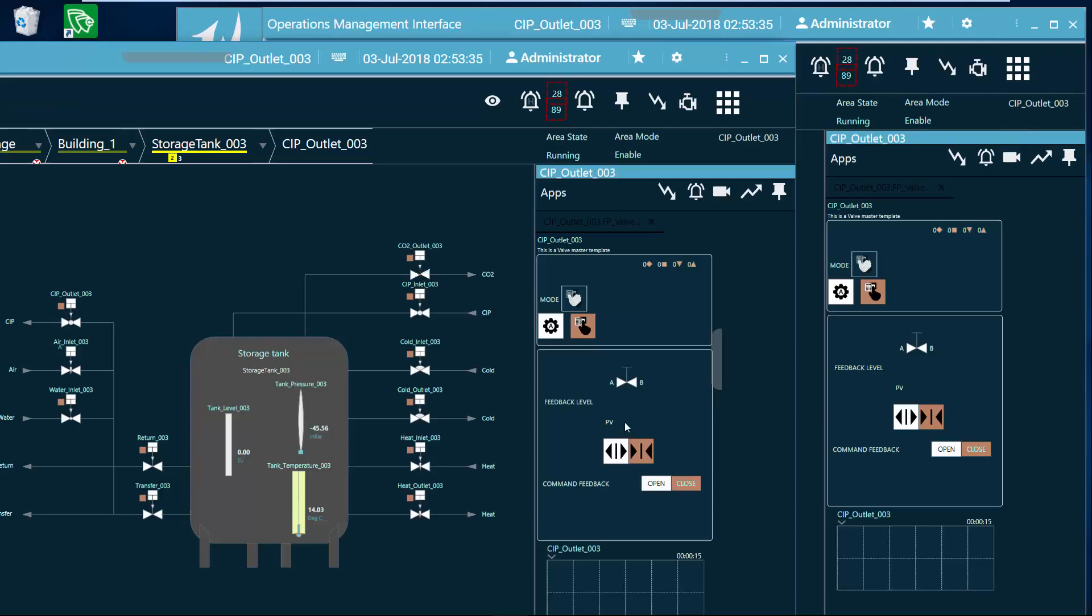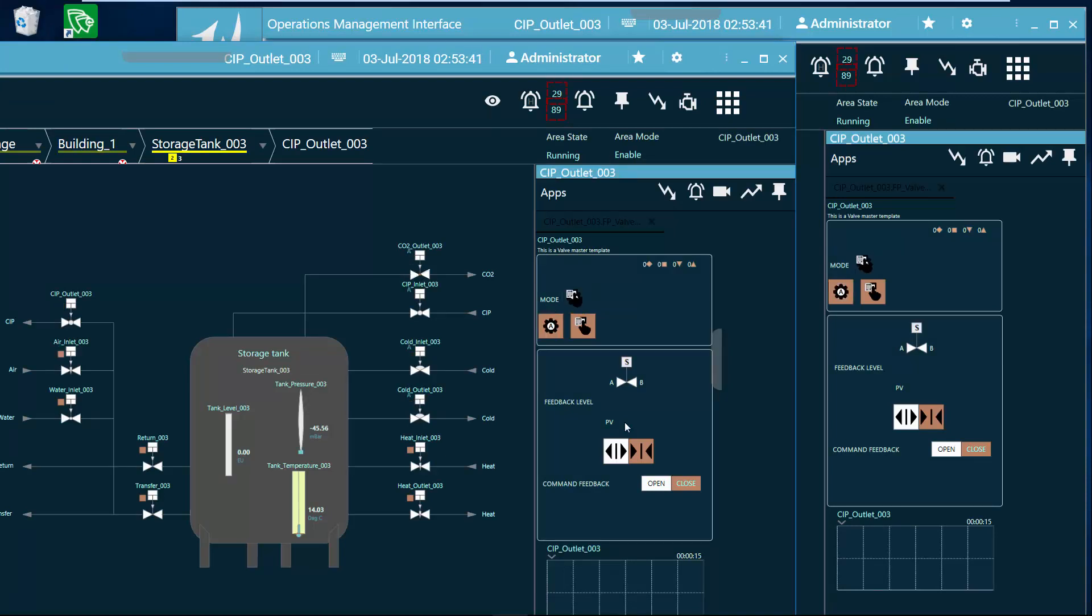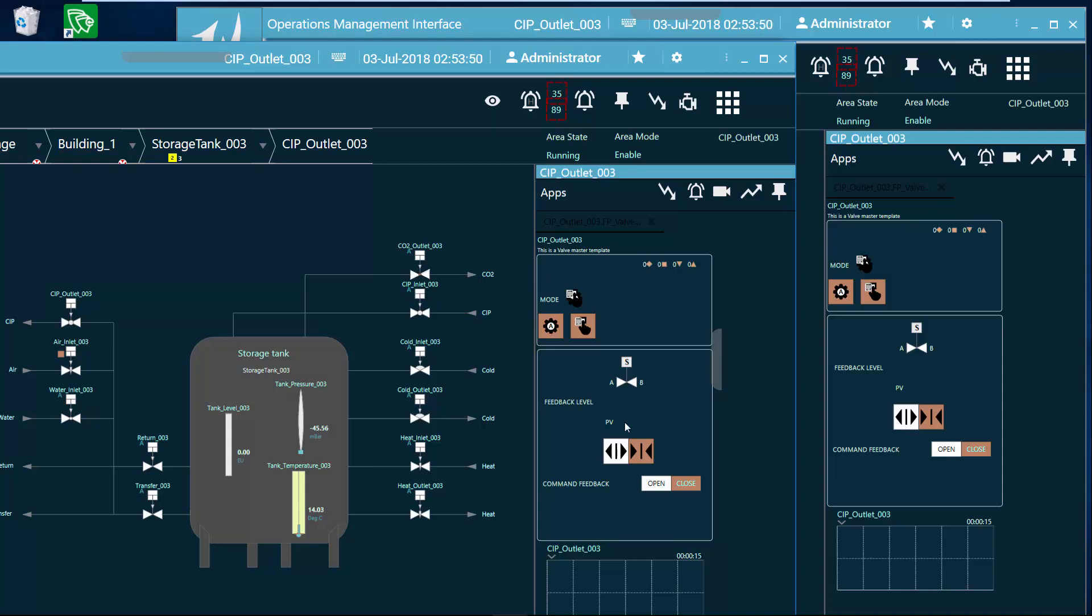What you see on the screen here is I have multiple instances of the OMI application running. This is something different than our classic InTouch application where we can only run one instance on a specific desktop. Now we can run multiple instances of OMI on a desktop, which is great if you have a multi-monitor situation and you want to have a separate instance running on another screen.